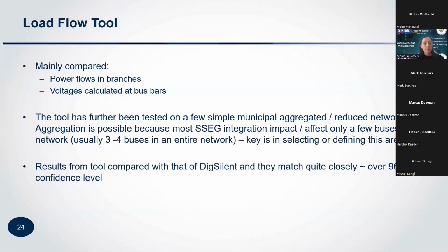Okay. The load flow tool looks at your power flow through your branches to determine if there are thermal violations. Also, it will calculate your voltages at each of the bus bars. The tool has been tested on a few sample municipalities where we aggregated the networks and ran some studies with SSEG connected. As mentioned, it would have to be aggregated to a 3 or 4 bus system. And then the biggest challenge probably would be to select the right network and to aggregate your network into a 3 or 4 bus system, and to make sure that those parameters are in place.